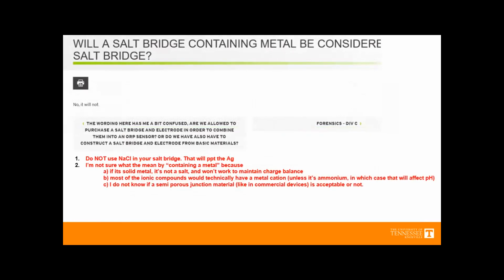salt bridge? We already talked about don't use sodium chloride in your salt bridge, because it will precipitate with silver. And I don't know what they mean in the question by containing the metal, because if it's solid metal, it's not a salt, and it won't work to maintain charge balance on the salt bridge. Most of the ionic compounds would technically have a metal cation, unless it's ammonium, and do not use ammonium nitrate. That's going to affect the pH of your solution, and that pH is then going to affect your ORP reading. I do not know if a semi-porous junction material is acceptable or not. So maybe not. I would try to make it with just a piece of string or a piece of paper.